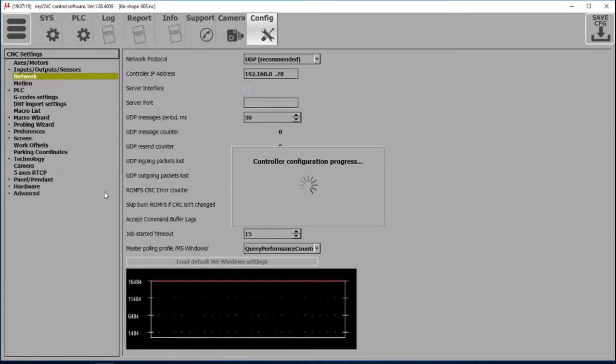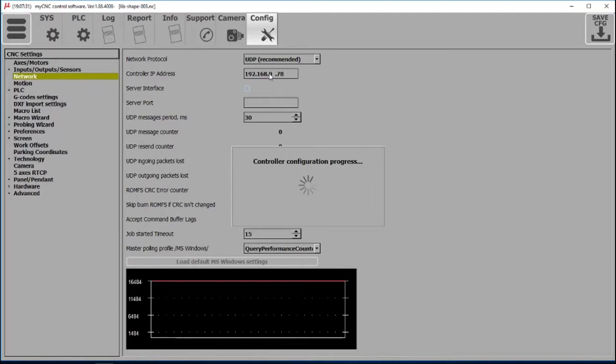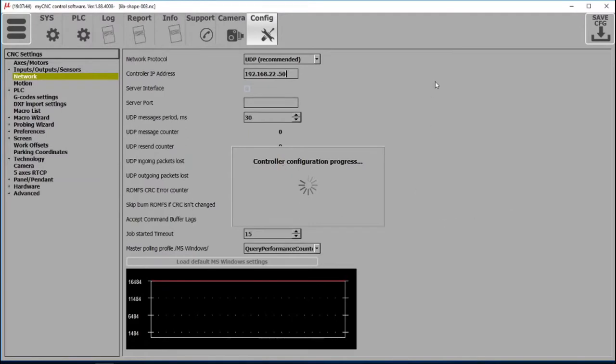Go to the controller IP address as previously described. You can just change the IP address there to the new 192.168.22.50. Again, this is the controller IP address. The computer IP address is separate and that's 192.168.22.51 in case of this example. Here you're just telling the computer that this is the controller address. This is where it should be sending its messages to communicate.